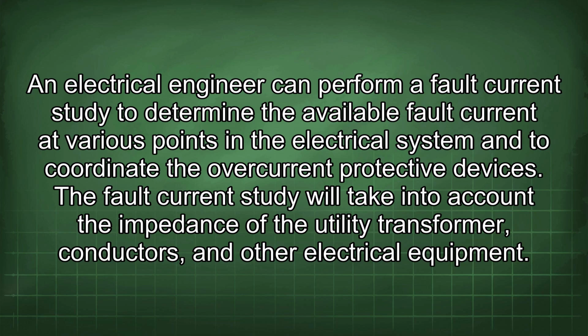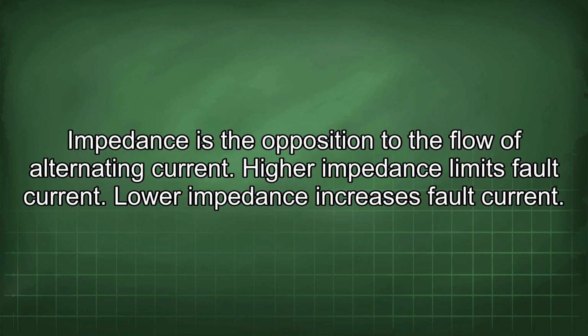An electrical engineer can perform a fault current study to determine the available fault current at various points in the electrical system and to coordinate the overcurrent protective devices. The fault current study will take into account the impedance of the utility transformer, conductors, and other electrical equipment. Impedance is the opposition to the flow of alternating current.